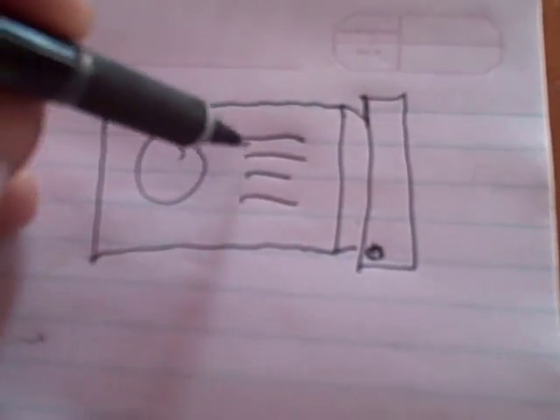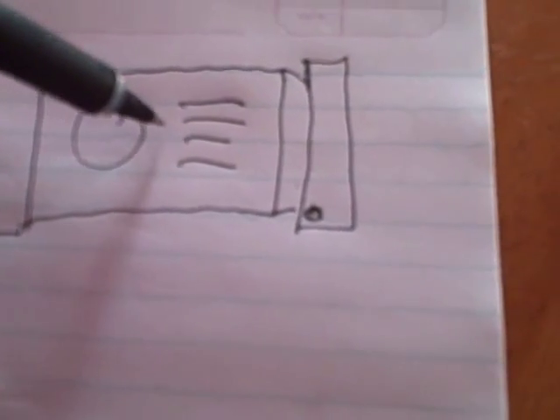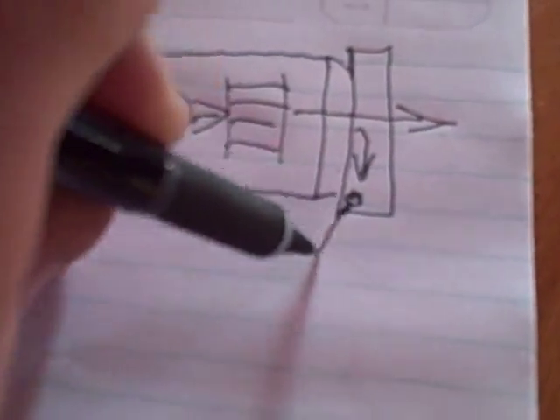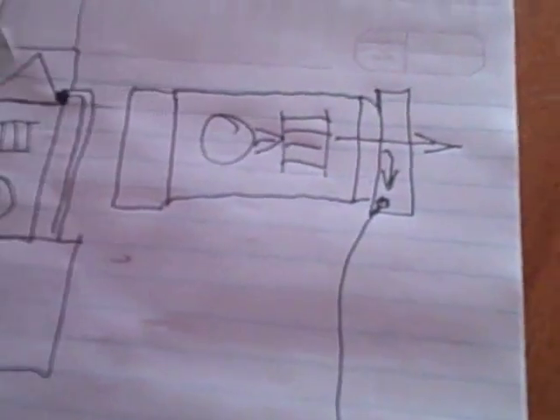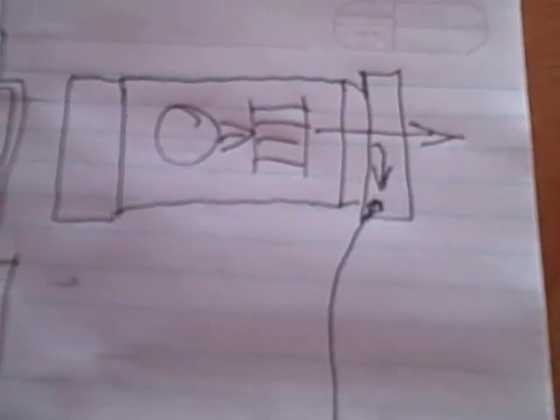You can do the same thing on a horizontal. You have a slab coil down here, the drain here, and the blower motor down here with electric heat strips. So the blower is forcing air through the coil - just always think of it in reference to the coil. You have positive pressure going through the coil, which also puts positive pressure on the drain, forcing water down. That's pretty easy either direction. Just always look at which way the air is blowing through the coil.